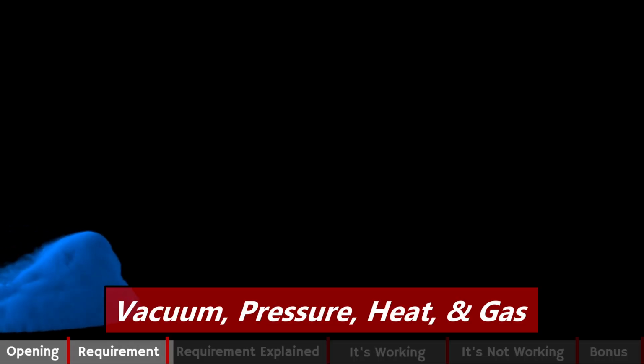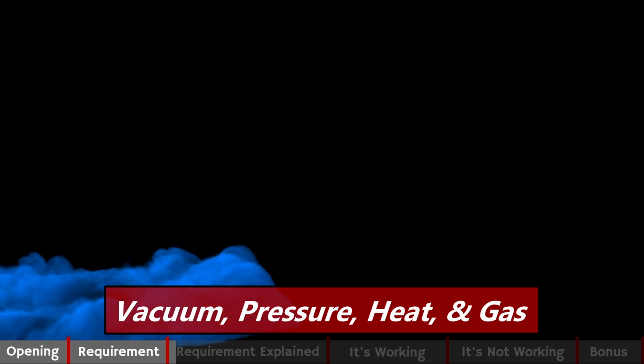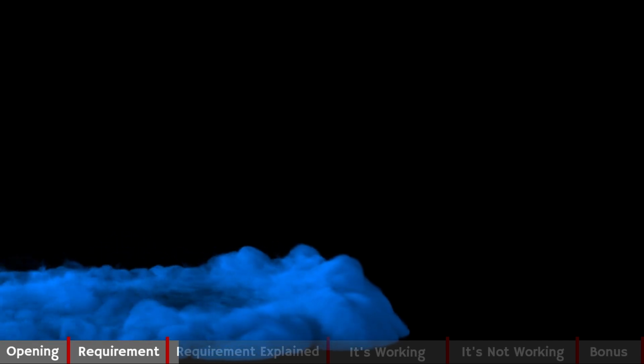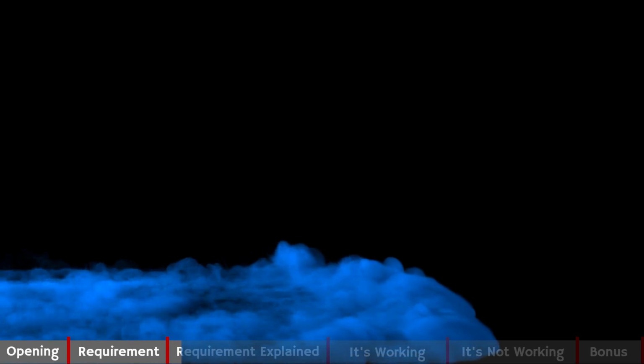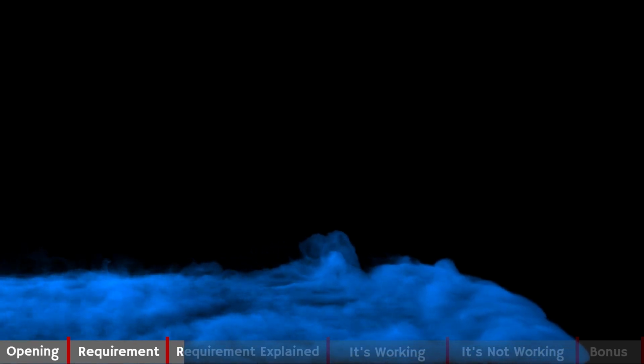Our topic, ethylene oxide sterilization, is covered by 13485 section 7.5.7. Ethylene oxide sterilization in five words: vacuum, pressure, heat, gas, sterilized. Ethylene oxide is another widely used sterilization process throughout the medical device industry. Ethylene oxide, or EO, is a chemical sterilant, a gas, which is injected into a chamber and allowed to permeate through the product, inactivating all microorganisms.